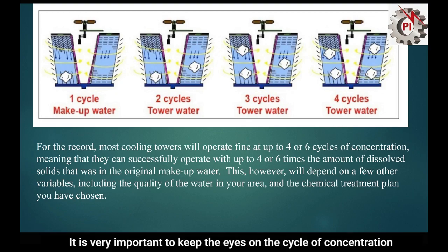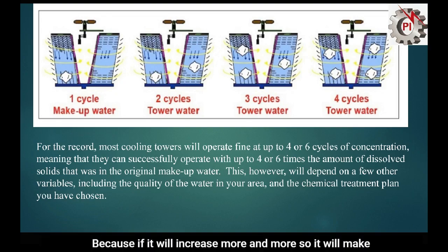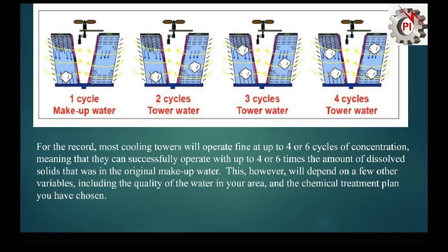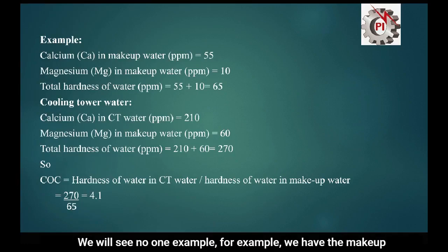It is very important to keep an eye on the cycle of concentration, how much the solid particles increase in the circulation water, because if it increases more and more, it will cause scaling and other biological problems for the water circulation. We will see one example now.